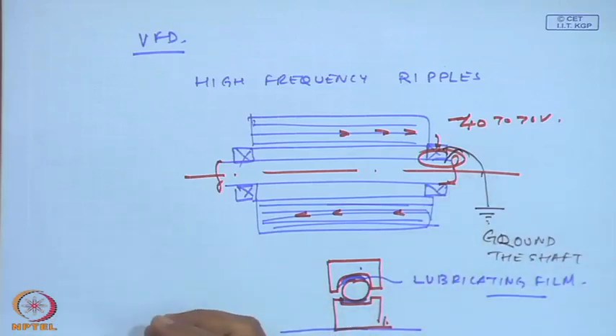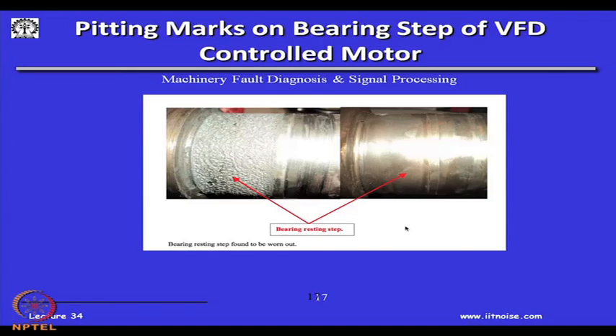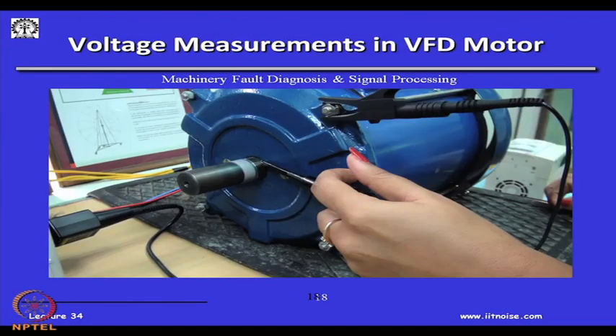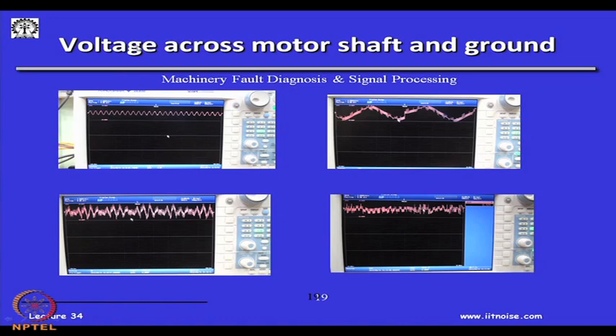Nowadays, of course, people are using VFD drives and they are coming up with situations where the bearings are having faults, pitting marks, or shafts are failing. What we did in our lab is we measured the voltage on the shaft, and then we recorded it. This is the voltage across motor shaft and ground in the normal case. But when you have the VFD drives at different frequencies, we have seen that these frequencies are there, and then they discharge and actually damage. These peaky voltages are as high as 40 to 70 volts, and they damage the motor shafts.